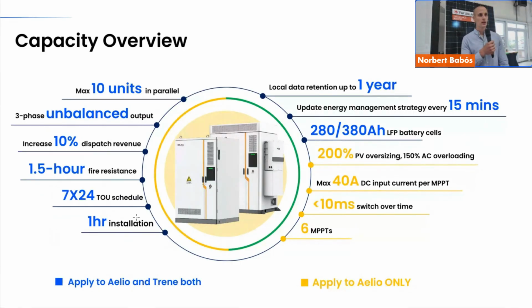So it's really a good advantage if you have, let's say, a 50 kilowatt inverter and you install 100 kilowatt peak PV panels. You can actually use 100 kilowatt at the same time, because you can feed back to the grid with 50 kilowatt, and you can store the electricity in the battery with 50 kilowatt at the same time. So basically, a 50 kilowatt inverter can utilize 100 kilowatt PV capacity. It also has the EPS function on the inverter, so you can use it in off-grid, and it can switch to off-grid mode in 10 milliseconds. So it's really just like the residential solutions, but on a large scale. And of course, you can connect multiple units in parallel if you need a bigger system.